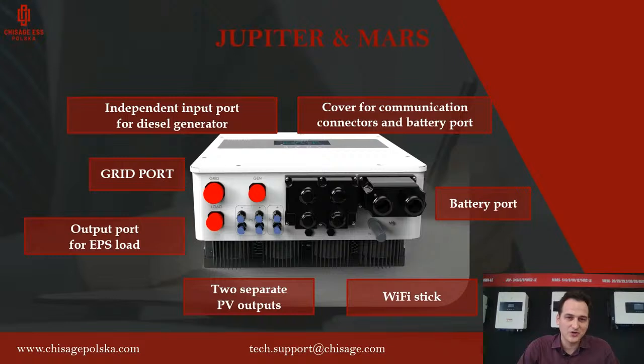If we look at the bottom of our inverter, we have the grid port. We connect the grid and the grid load from this side. We have the load port where we connect the backup load. All the EPS load is supported on grid and off grid also. And this GEN port is a combined port. We can connect the generator, we can connect the smart load, and also we can connect another on-grid installation, so we can do AC coupling.